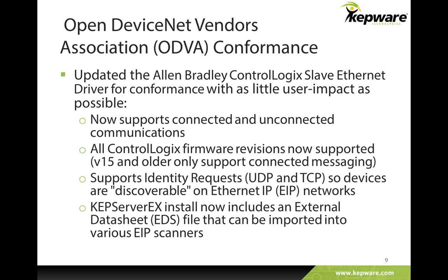One question here: what's the difference between connected and unconnected messaging? Right, so connected means you open the path for communication, open the TCP sockets, and keep those open for that messaging. A lot of people who use Allen Bradley say that's faster since that line stays open. And unconnected means you open that line of communication and then close it. That's the basic difference. Some people say connected is faster. Any other questions there?